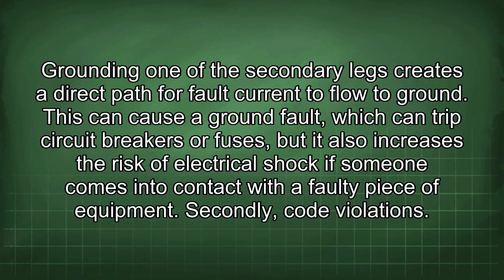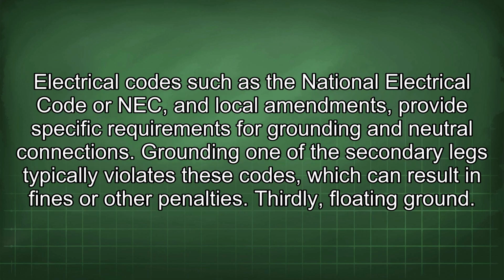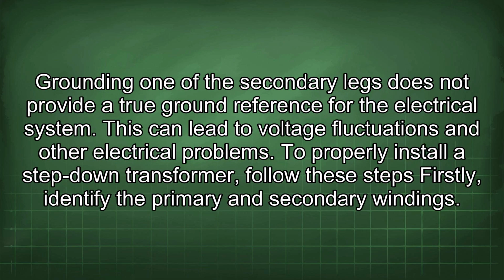Secondly, code violations. Electrical codes such as the National Electrical Code, or NEC, and local amendments provide specific requirements for grounding and neutral connections. Grounding one of the secondary legs typically violates these codes, which can result in fines or other penalties. Thirdly, floating ground. Grounding one of the secondary legs does not provide a true ground reference for the electrical system. This can lead to voltage fluctuations and other electrical problems.